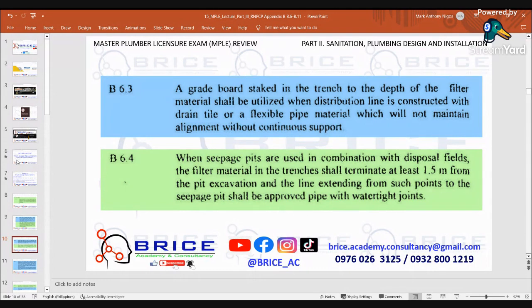Where seepage pits are used in combination with disposal fields, the filter material in the trench shall terminate at least 1.5 meters from the pit excavation, and the line extending from such points to the seepage pit shall be approved pipe with watertight joints.